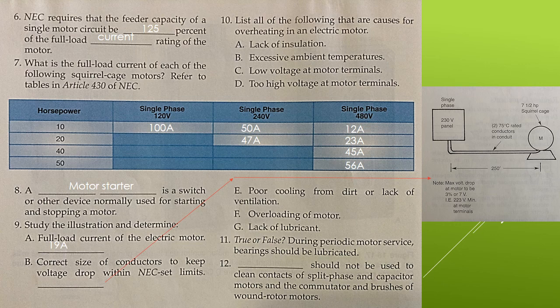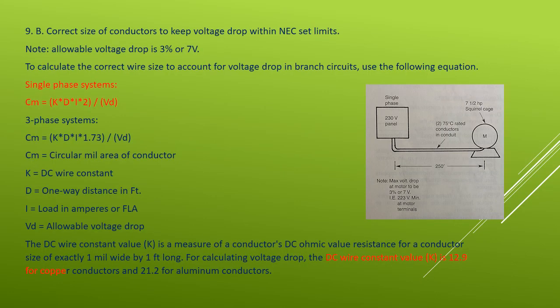Part B of question 9, correct size of conductors to keep voltage drop within the NEC set limits. The NEC set limit is 3% or 7 volts. To calculate the correct wire size to account for voltage drop in this branch circuit, we use the following formula. I know this is a bit different from what the text described, but I believe it is a bit more straightforward, and you can acquire the same result.